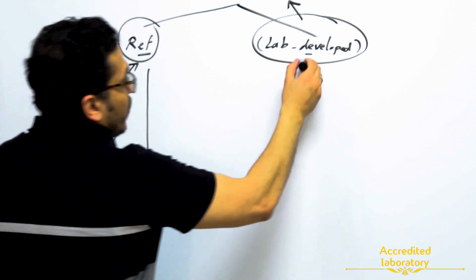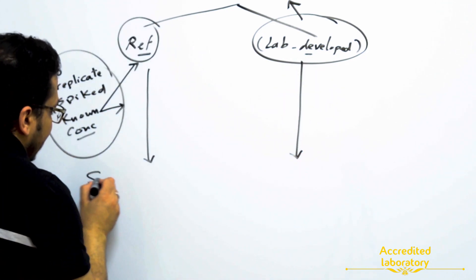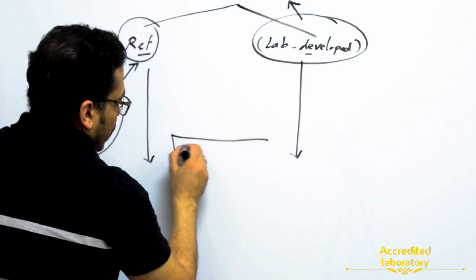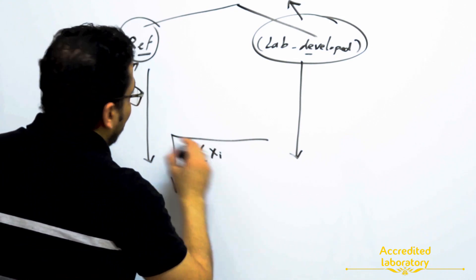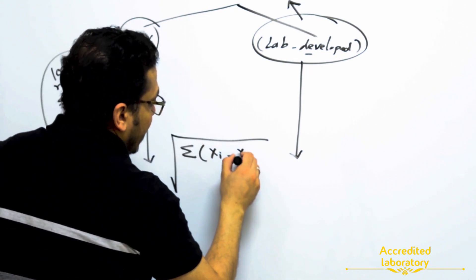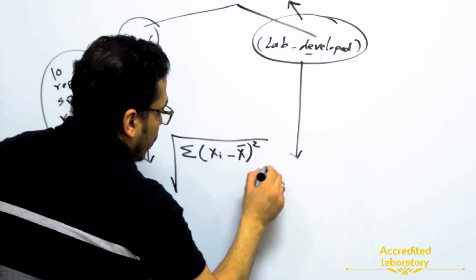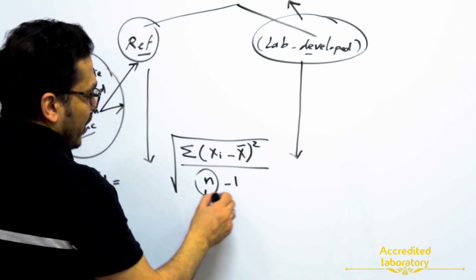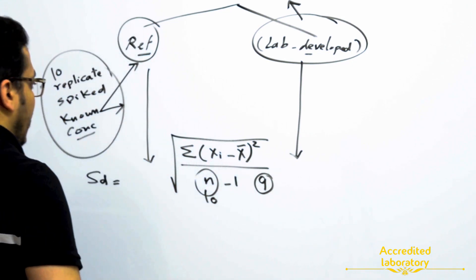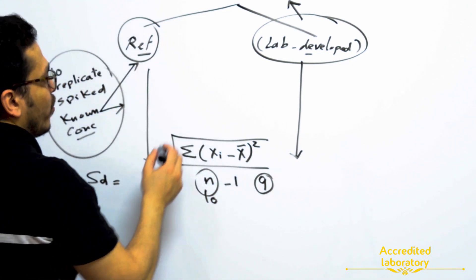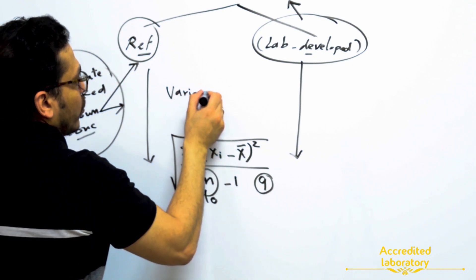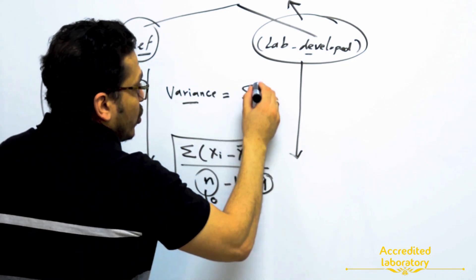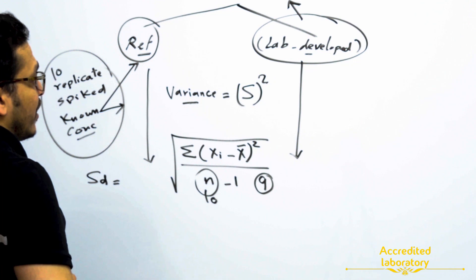These 10 replicates will be analyzed by the reference method and also by the lab-developed method. You will get the results from the instrument. Then you will calculate the standard deviation for each group, which is equal to the square root of the summation of each individual result minus the average, divided by n minus one — the degree of freedom — where n is 10, so equal to 9. Then you will calculate the variance for each group, which is equal to the square of the standard deviation.